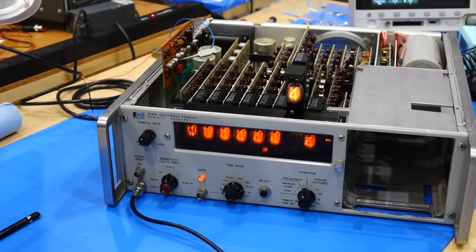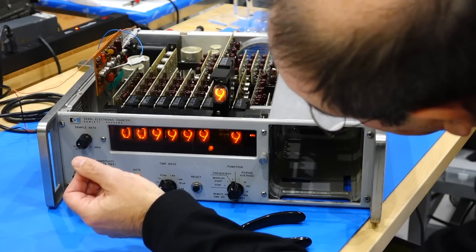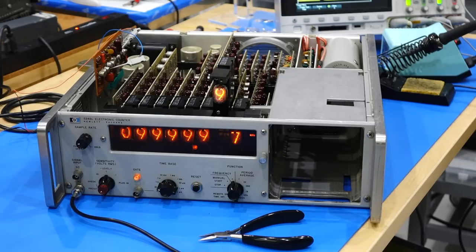Okay, I have reconnected my reset over here, and it's in very, very close calibration. So I bet you someone did all the rest of the calibration. Power supply was spot on, the oven oscillator is spot on, and then somehow there were 8 or 9 failures in the rest of the machine. Excellent! I think we repaired the main parts.